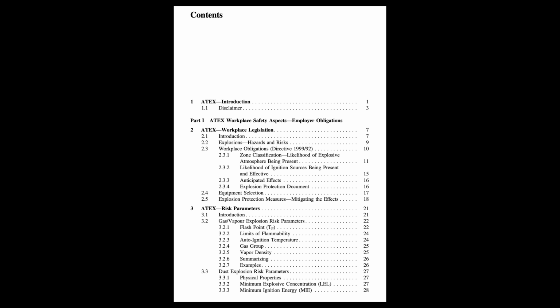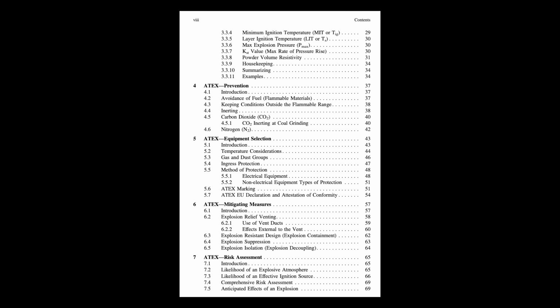And what about dust zone classification specifics? You mentioned the challenges with settling. Yeah, defining dust zone extents is trickier than for gases because dust doesn't just disperse, it settles, then it can be kicked up again. So housekeeping becomes a major factor. How clean the area is kept.